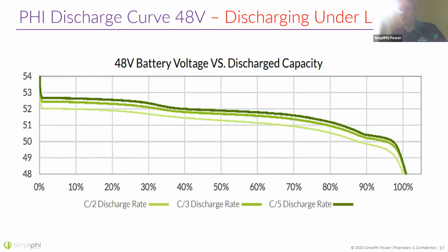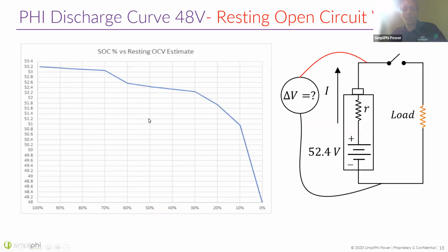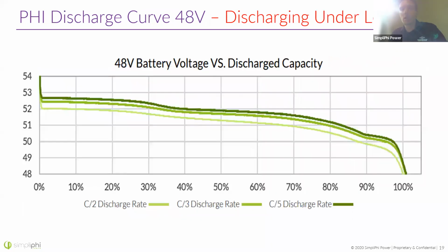So if you want an accurate measure of your battery bank's state of charge, stop loads and measure the voltage, and you can use this curve to figure out what the state of charge is. But if you're loaded, it's a little more complicated, and that's why voltage doesn't tell you everything.